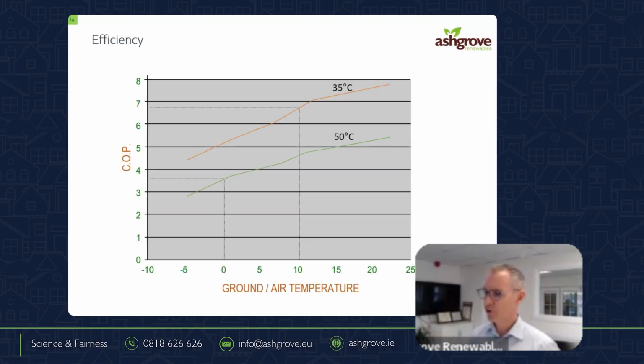So now, here's a graph. We won't spend too much on it, but I just wanted to put it into a simple graph. I'll go back one. If I have a heat pump and I'm running at 35 degrees, so this is our condensing temperature coming off the hot side of my heat pump, and, simplistically, if the outside air is 15 degrees, if I come up and hit this graph, you can see here, if I'm running the heat pump at 35 degrees into, say, underfloor heating, I have a COP of 7. Now, I should keep in mind, that's great news, Shane, at 15 degrees when it's already warm. Fair enough, point taken, but it is possible.